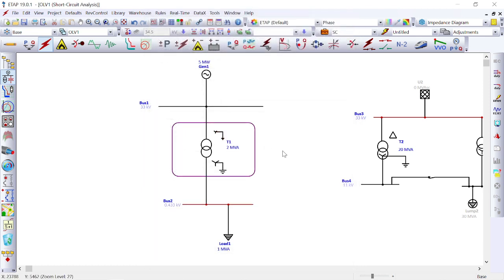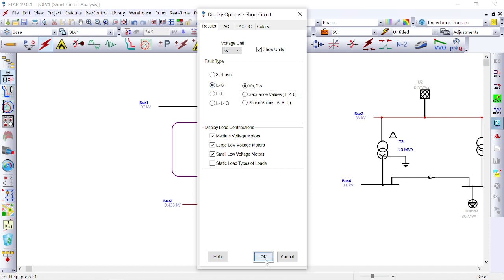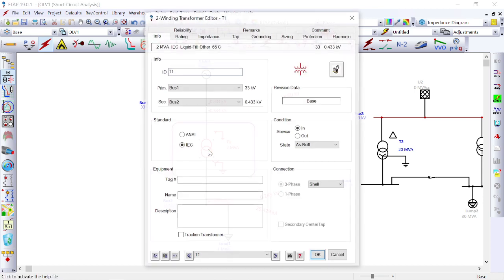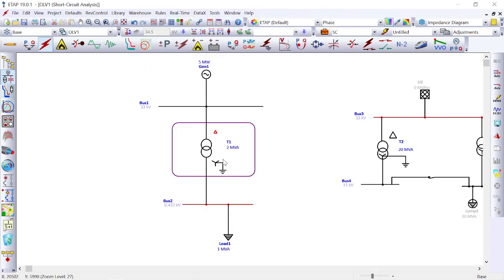Let us see this in simulation. We will do a short circuit analysis on the transformer. If we take star winding instead of delta and then apply a line-to-ground fault using IEC 60909, we can see 0.334 kA of fault current on the load side bus. When the fault occurs, we can also see the impact and fault current on the generator or inverter side.